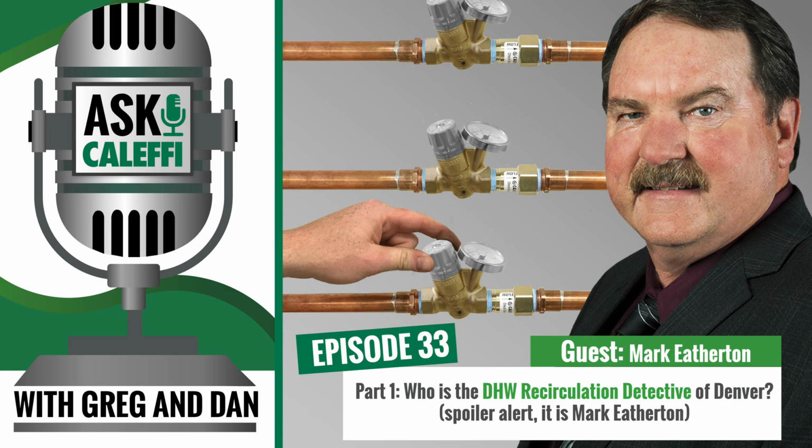Well, we had an interesting tech call come in from a local project to us here in Wisconsin, and it was a hotel, and they have one of our Legio Mix electronic mixing valves on site, and it's been working perfectly. They've had no hot water complaints or issues, and suddenly the contractor got a call of no hot water or low temperature hot water, and then the next day he got a call again, and they were determining what we were able to do because our Legio Mix has data logging. It stores the temperature histories. We're able to walk him through that.